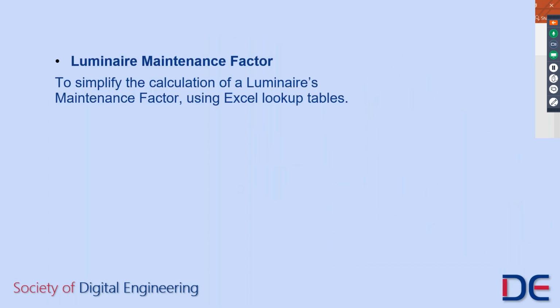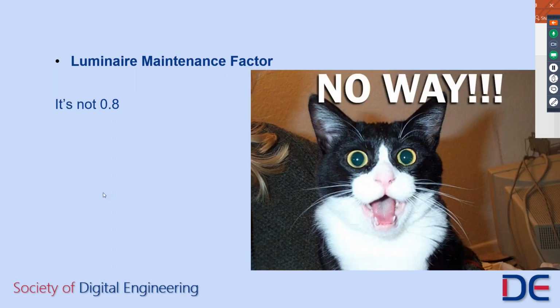Okay, let's look quickly at the maintenance factor for luminaires. Here, I'm just going to use a simple Excel sheet, which I believe is now available from the Society of Light and Lighting via the CIBSE website. It should be free to download. So first things first, luminaire maintenance factor, it's not 0.8. I know that's the number most people put in as a rule of thumb, but there are actual ways of calculating this, and 0.8 isn't always the right answer.